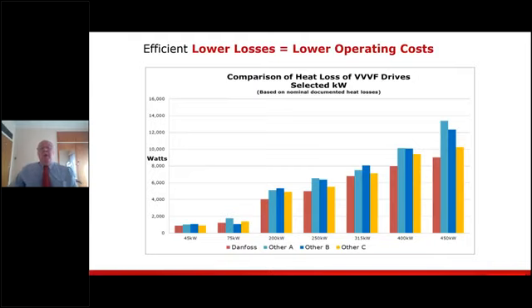Now, quite often when I'm in discussions regarding variable speed drives, I often get the comment, a drive is a drive. In other words, they are saying all drives are the same. Well, that's actually not true, because the high efficiency and the resulting low power loss minimizes the heat load on the switch room's air conditioning and its ongoing operating costs. So simply comparing stated efficiency ratings of variable speed drives from different manufacturers can actually be misleading, because they will all typically state that they're in the 96 to 98% range. But the factors included in those ratings can be different from one manufacturer to another.